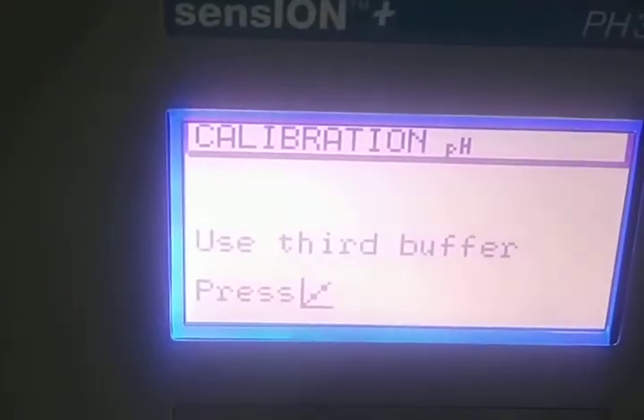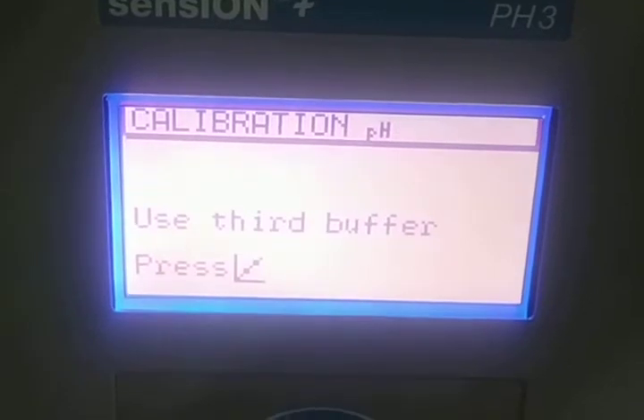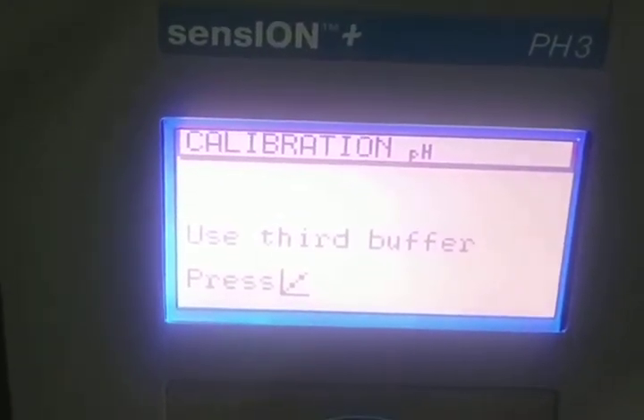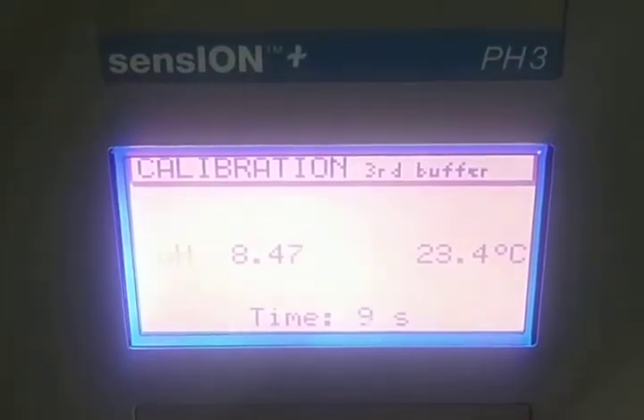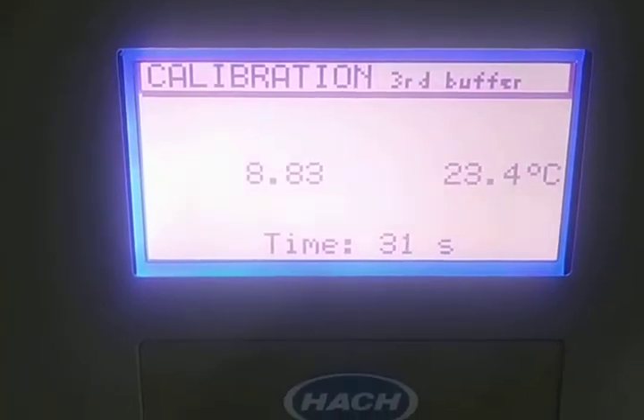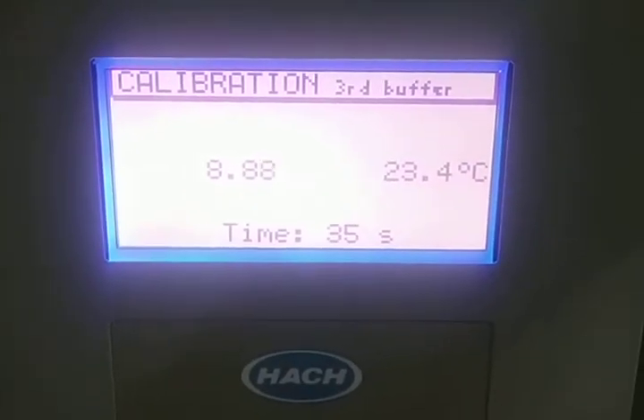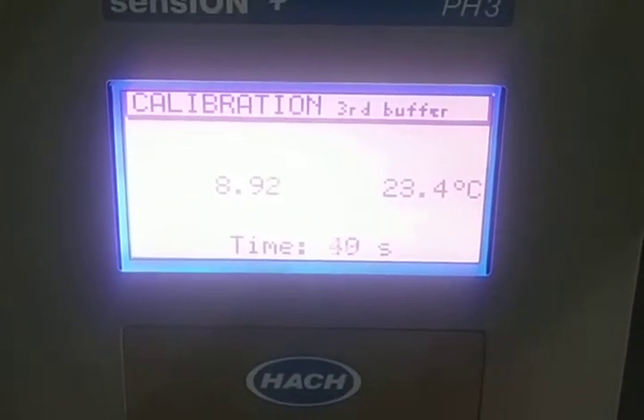So that means we will be calibrating the instrument. For calibrating the instrument, which button do we need to press? Yes, this button. Before pressing that, you need to make sure the display shows use third buffer solution. That means the third buffer solution should be pH 9.2. That is being placed. Now you need to press the calibration button. Once it is pressed, the instrument will be getting calibrated for pH 9.2. So it will take some time. So this is how the setup will be. As I told, the stirrer is inbuilt, so I need not mix the solution. The value to which this instrument will get calibrated is 9.2 for the third buffer.